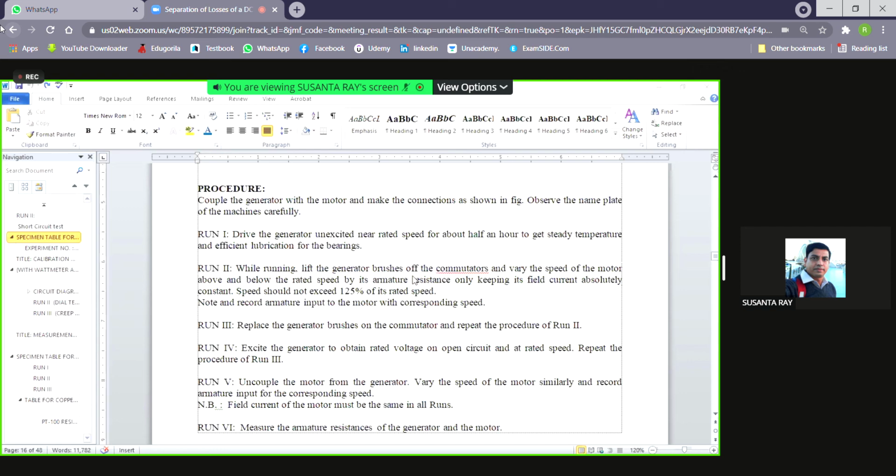এবার জেনারেটরের ফিল্ডটা যদি এক্সাইট না করি, তাহলে generator flux will be very minimum, only the residual flux, only 2% of the flux. So in that flux we can have some flux reversal, but that is very small. So that means your eddy current and the hysteresis loss will be minimum, core loss will be minimum for the generator.